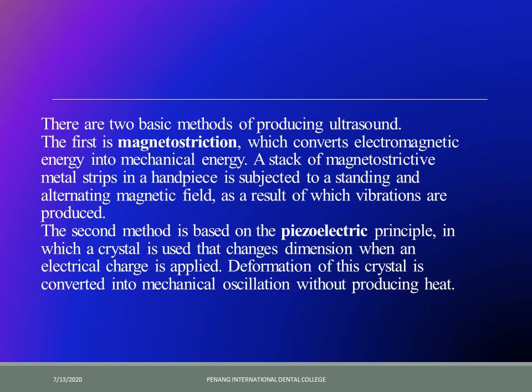There are two basic methods for producing ultrasound: magnetostrictive and piezoelectric. The piezoelectric is more advantageous and is what we use because heat generation is lesser and the movement it creates is more favorable in dentistry. The magnetostrictive converts electromagnetic energy into mechanical energy — metal strips in the handpiece are subjected to a standing and alternating magnetic field, producing vibrations.